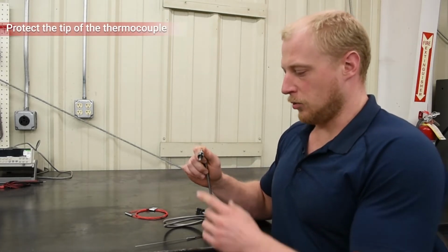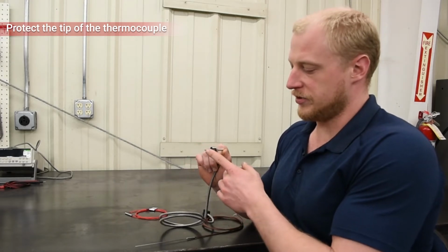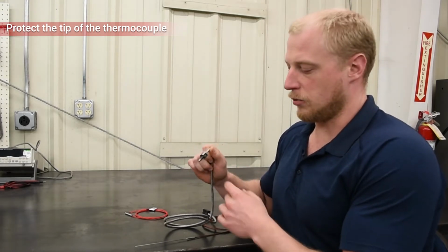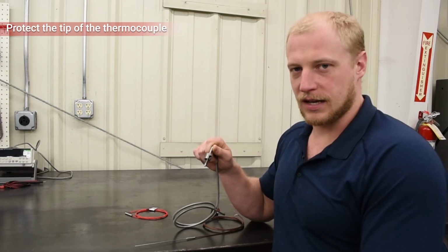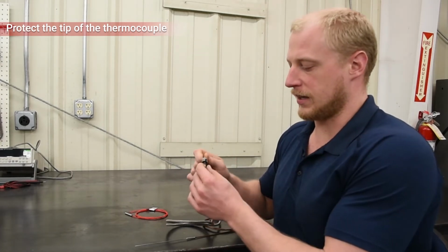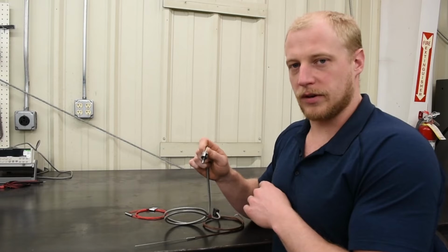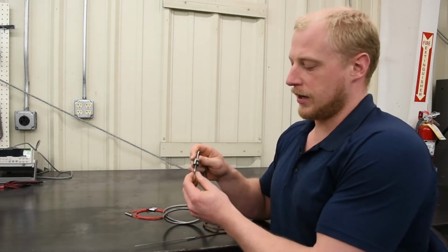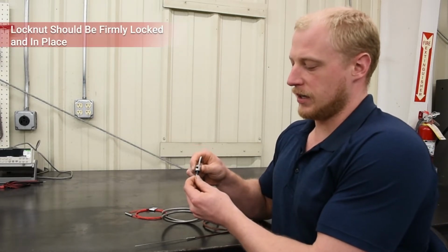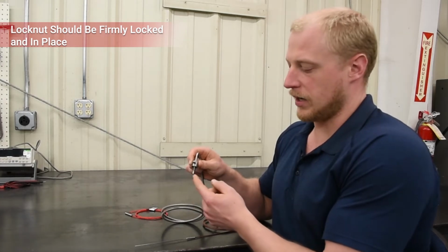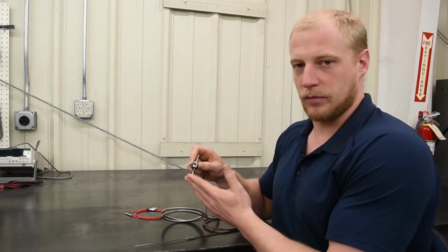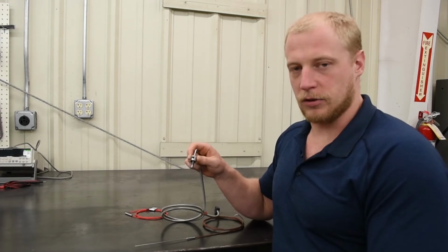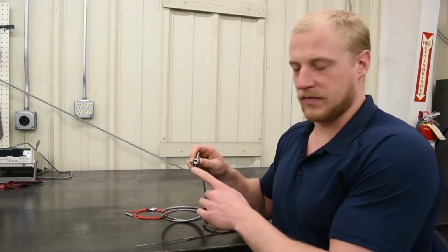This has a drill tip. You don't want to deform this tip in any way, or mash it into anything hard. It should fit into the bottom of a drilled hole. This has a lock nut—make sure it's firmly twisted and in place, with good contact on a solid metal surface. That will give you good lifetime out of the end of this sensor.